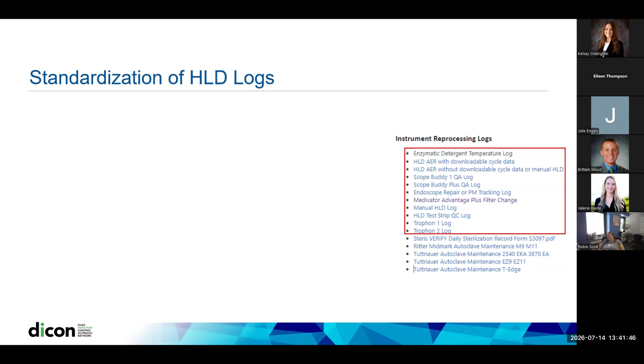As I've mentioned, one of the more challenging obstacles that we had to wrangle was the variation in existing logs. High-level disinfection practices can be very complicated, as we all know. And with over 100 clinics in this group, half of them were performing some form of reprocessing. So the challenge was to develop tools that could be applicable across all sites and took into consideration all types of devices. On the right is a list of the logs that were developed specific for high-level disinfection, and we provided samplings of those logs for review.